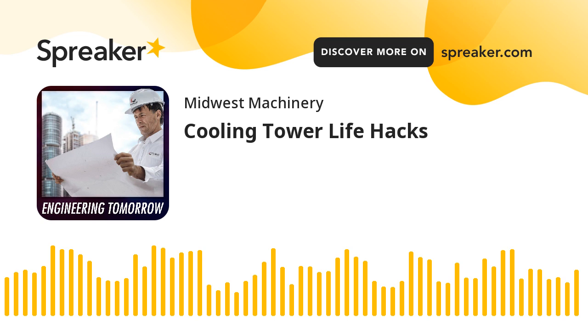First question: from a specification standpoint, is the 15 mil measurement before or after forming? It's before forming. It's a roll of a giant sheet of PVC. When we're allowed to again, Marley's got an awesome tour at the Olathe plant where you can see the fill being made, vacuum formed across a mold. So it's a really good question. If you start with 12 mil and pull it across a form, inherently the bends and angles are probably going to be a little narrower than the 12. So that's another reason why you should specify 15 mil. It's prior to forming that's the only time you can really measure that, because once you form it, there will be areas a little thicker and a little thinner throughout that chevron shape.